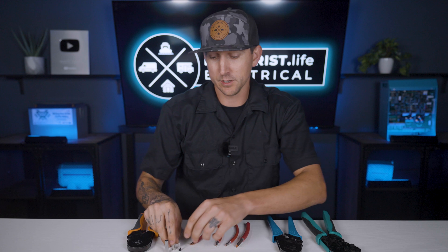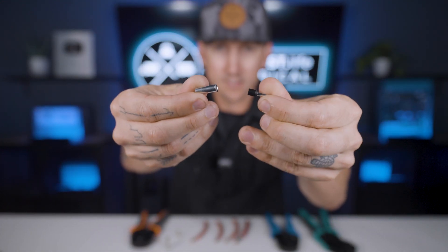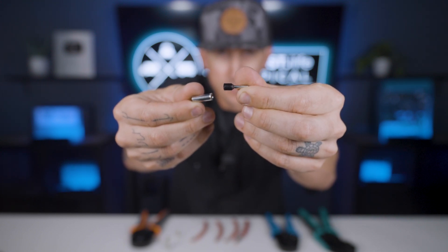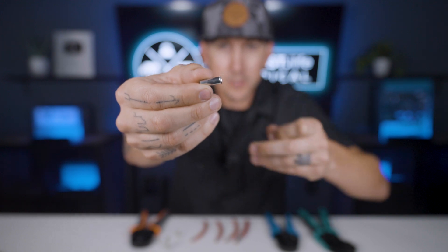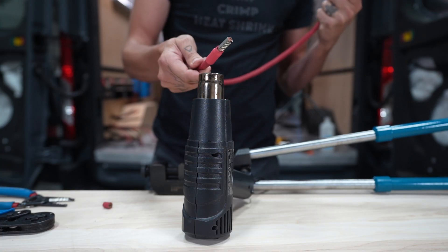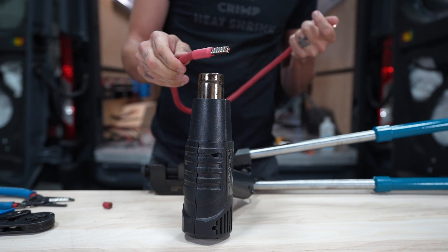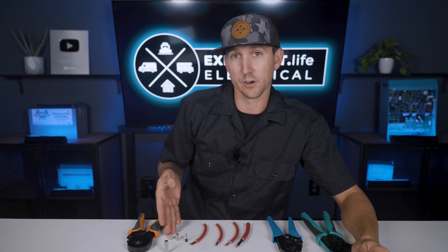Ferrules come in two different types: insulated ferrules and non-insulated ferrules. Insulated ferrules have a nylon collar pre-attached to the ferrule, and non-insulated ferrules do not. Typically a bit of additional heat shrink would go onto a non-insulated ferrule for extra strain relief and protection, but that's not always the case — it really just depends on what type of component you're connecting to and the shape of the terminal.